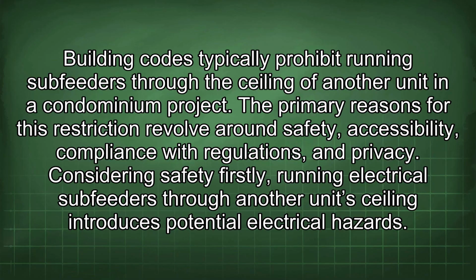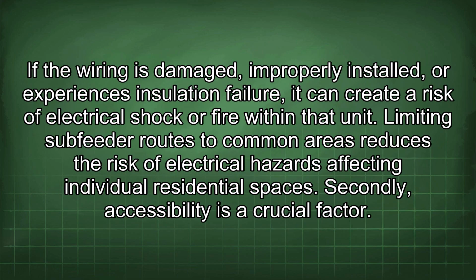Building codes typically prohibit running subfeeders through the ceiling of another unit in a condominium project. The primary reasons for this restriction revolve around safety, accessibility, compliance with regulations, and privacy. Considering safety firstly, running electrical subfeeders through another unit's ceiling introduces potential electrical hazards. If the wiring is damaged, improperly installed, or experiences insulation failure, it can create a risk of electrical shock or fire within that unit. Limiting subfeeder routes to common areas reduces the risk of electrical hazards affecting individual residential spaces.